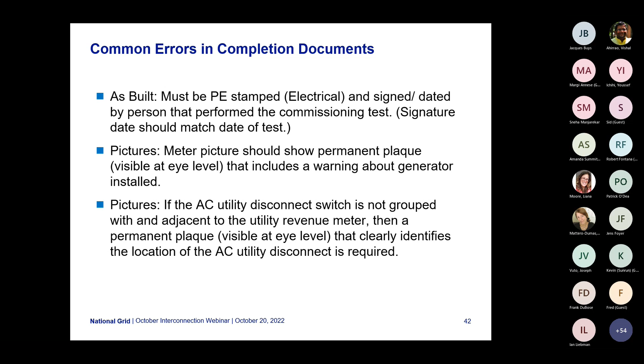Again, reminder that the as-built must be PE stamped and signed and dated by the person that performed the commissioning test, with the signature date matching the date of the test. With respect to the completion picture package, the meter picture should show a permanent plaque visible at eye level that includes a warning about the generator that's been installed. If the AC utility disconnect switch is not grouped with and adjacent to the utility revenue meter, then a permanent plaque visible at eye level that clearly identifies the location of the AC utility disconnect is required. Next slide, please.